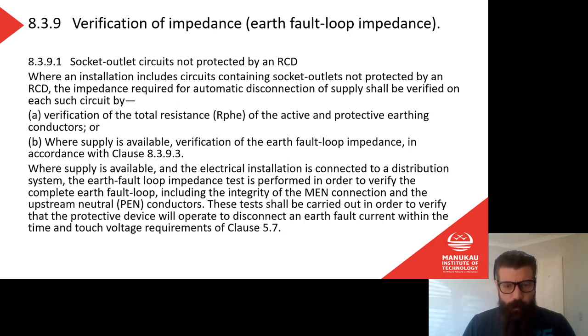That makes sense. Now, how much current is going to flow in that circuit when I have a short circuit? If I touch the red and the black wires together, how much current will flow? Well, that depends. It depends on the resistance. We've very briefly touched on this, that current is voltage divided by resistance. So the higher the resistance, the lower the current flow will be. But I definitely need to have a high current in there, otherwise the circuit breaker is not going to trip, which is really bad. So what we need to do is test what the resistance of that circuit would be. What is the resistance of that whole wire all the way back to the point of supply in the event of a short circuit? Now again, how we do this and all of the stuff around it is not worth going into now, but what I can tell you is an earth fault loop impedance test is a test of what is the total resistance in that circuit, how much current is going to flow if there's a short circuit, and then I can use that to work out, am I getting enough? Is this going to be enough to blow the circuit breaker?